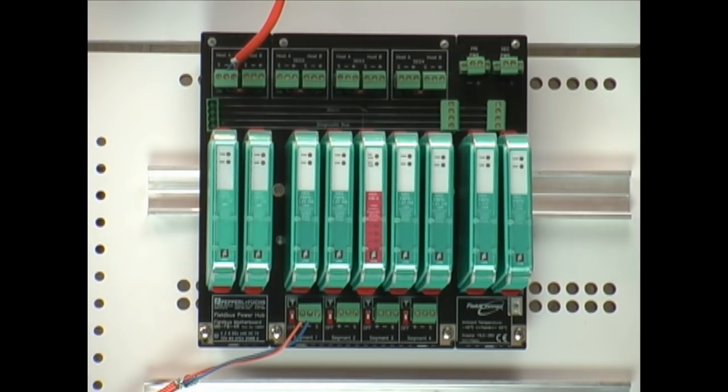Power supplies main goal is to provide a matching impedance for the field bus segment. If you just connected up a bulk power supply your communication signal would be lost and there would be no viable communication to control your plant.